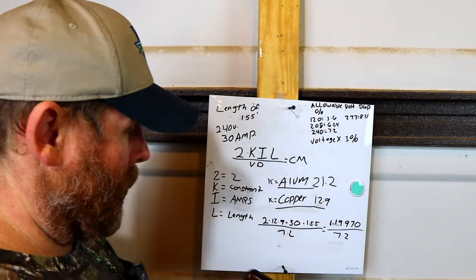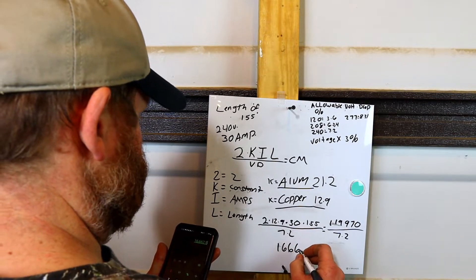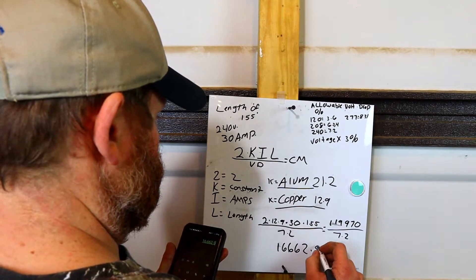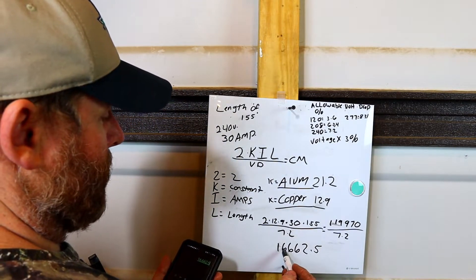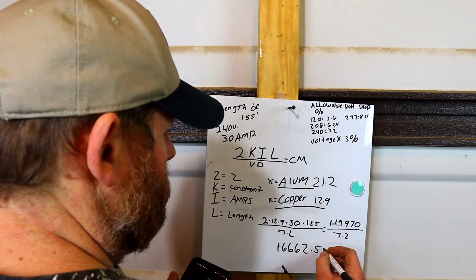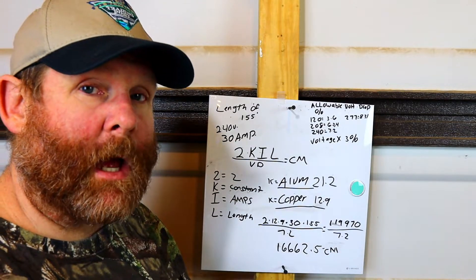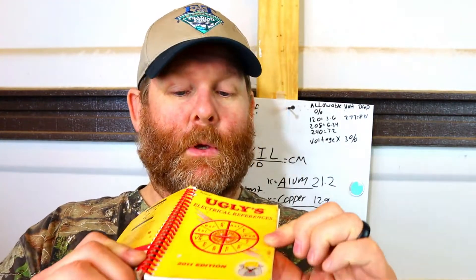We're going to get a whopping number of 16,662.5. Now that number is circular mils. So now we have to go to Chapter 9, Table 8 in our code book. I'm using the 2011 edition — you can look in Chapter 9, Table 8, that is where the circular mils information is. It's also in my Ugly's book, 2011 edition, on page 71.